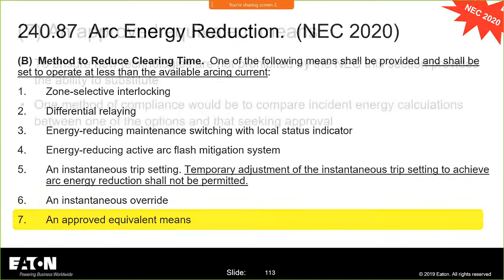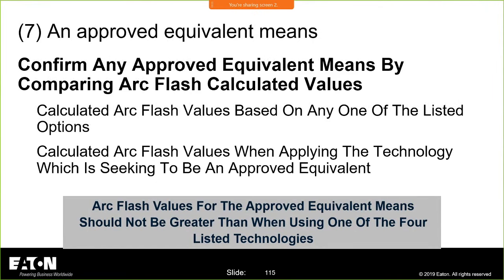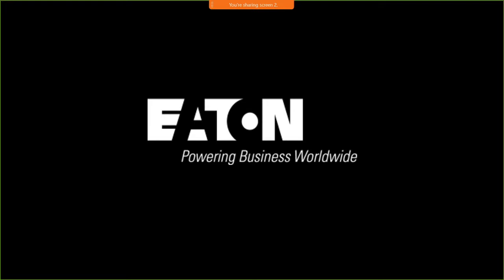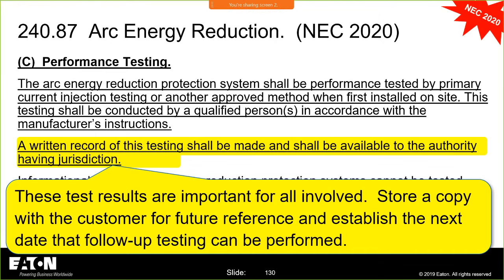Seeing if there's anything else. Approved equivalent means. Let's end on this one. If I have my new technology, one of the methods that I would use is to say you could calculate an arc flash value based upon this new technology and compare that with the incident energy calculated with, say, zone selective interlocking or differential relaying or whatever the other technologies that you're using. Or you could say, here's my pickup points for my technology and compare those. So those are just the different ways that you can help the inspector understand when your new technology should be permitted.